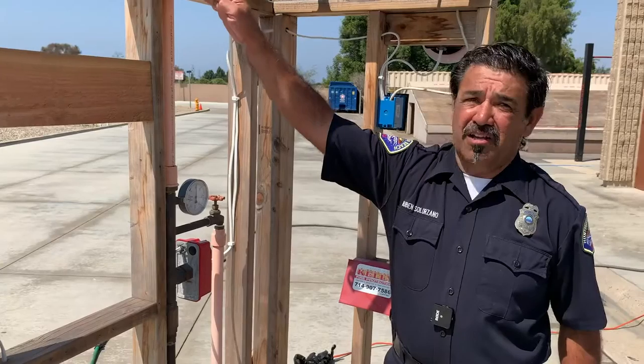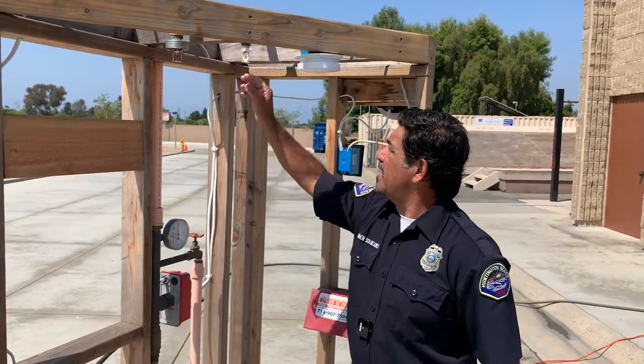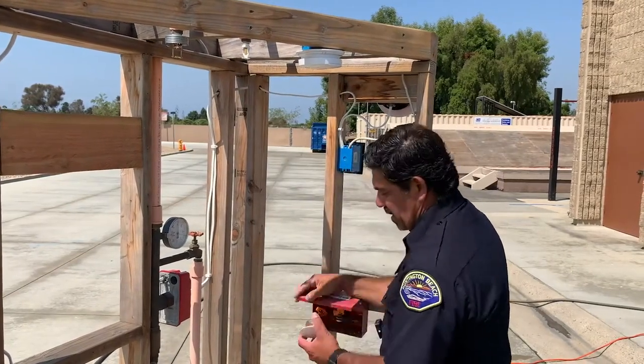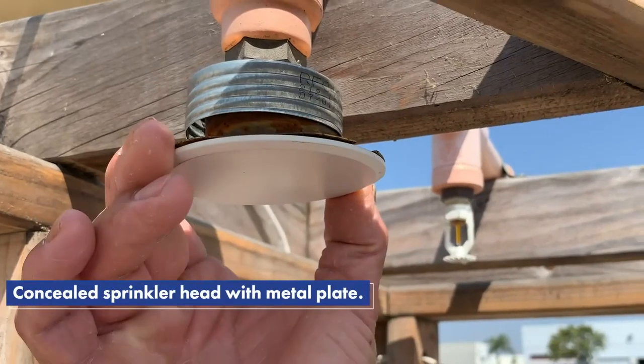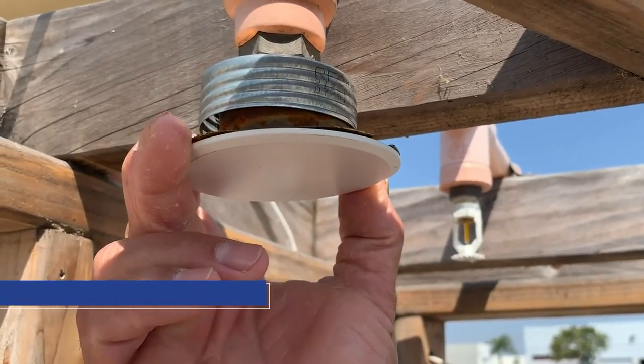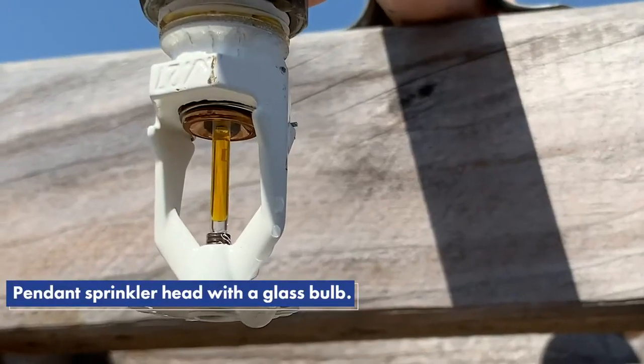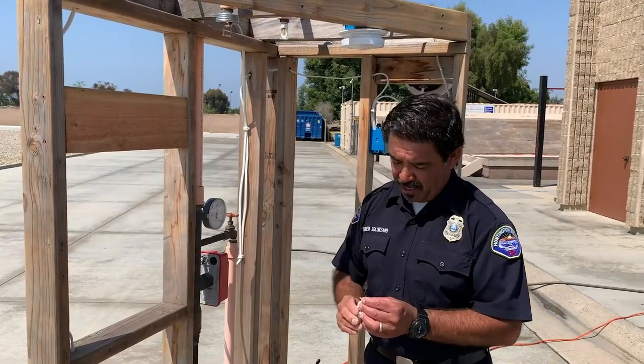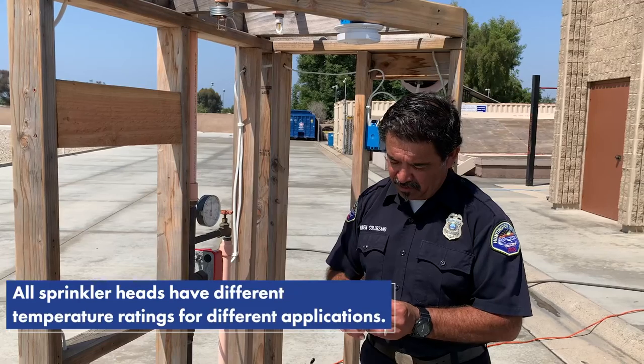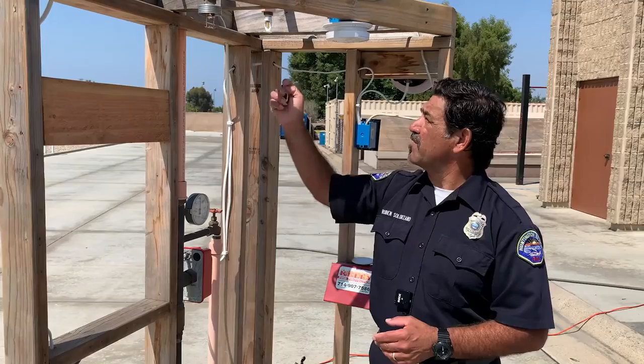These are common residential sprinklers. We have the concealed head and the pendant style. The concealed head will have a cover that goes over it to help camouflage it in the ceiling. The concealed head has a little metal plate and the pendant has a glass bulb that are set to melt or break at the degree set on the head. This one is 175 degrees — when it hits 175 degrees it will activate the sprinkler head.